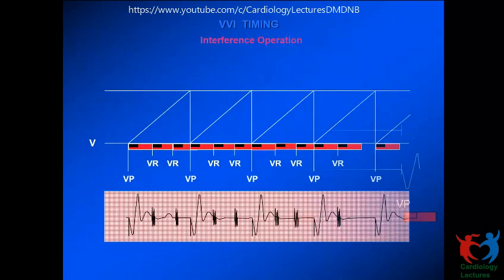And if there's electromagnetic interference that happens periodically like this, in this case, it delivered a V pace, it started a refractory, and the lower rate timer also started. But before the expiry of the refractory, there was a noise, electromagnetic interference, and it restarted one more refractory. And there is another electrical impulse that came from outside the heart, and it is also in the refractory. It started one more refractory, so it ignored both of these. The pacemaker never had an opportunity to reset the clock, so it actually delivered a V pace. This is what is called noise reversion.